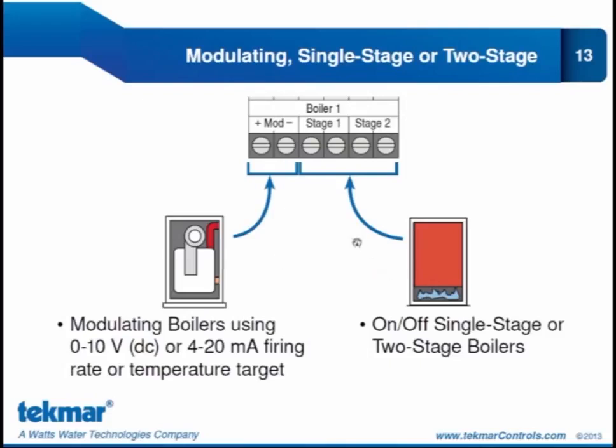On-off boilers are connected to the stage 1 terminals and or the stage 2 terminals. If we have a single stage boiler, we will connect directly to stage 1. If we have a 2-stage boiler, we will connect to stage 1 and stage 2.